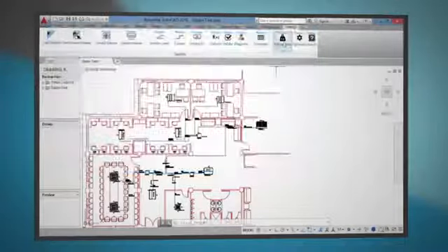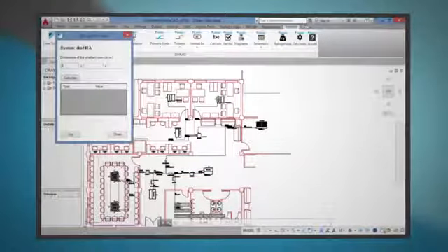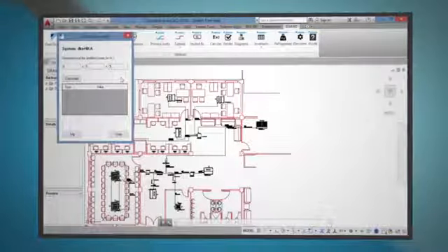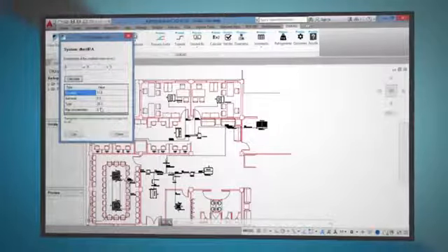You can also calculate how much additional refrigerant will be required on site. You can even check compliance with EN 378 to ensure that for hotel projects, for example, you can eliminate the need for expensive leak detection.